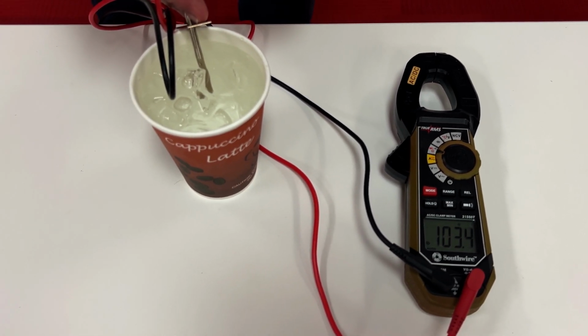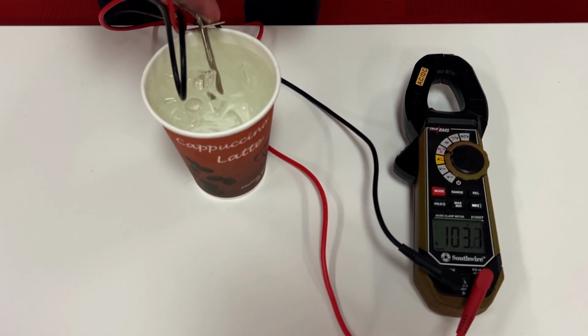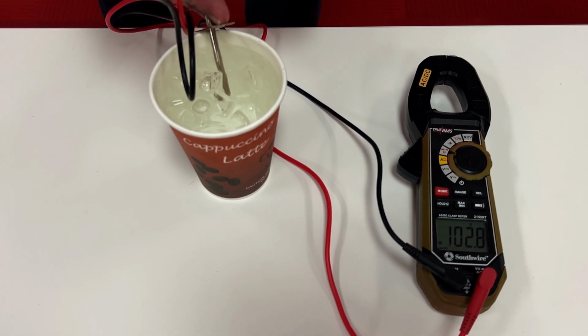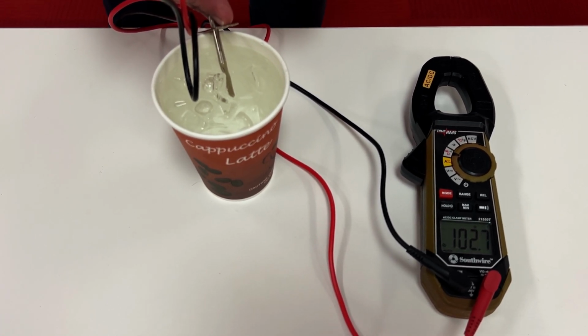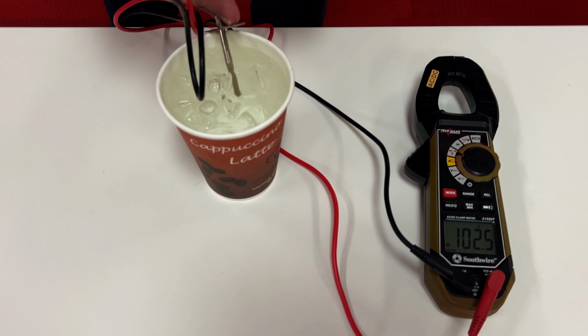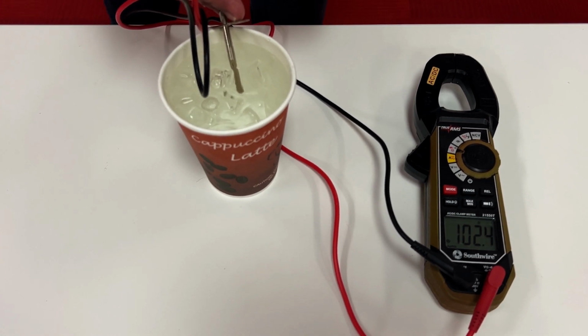After about 45 seconds or so, it should read somewhere between 98 and 102 ohms. As long as it's reading between 98 and 102 ohms, the probe is good. If it is outside of that range, the probe has failed and will need to be replaced.